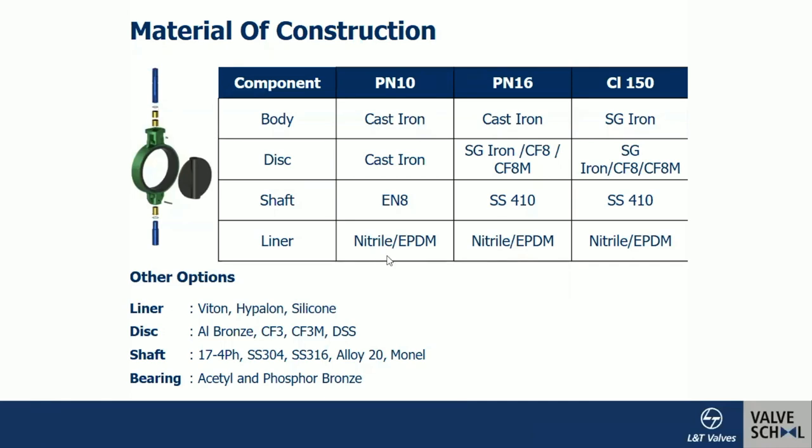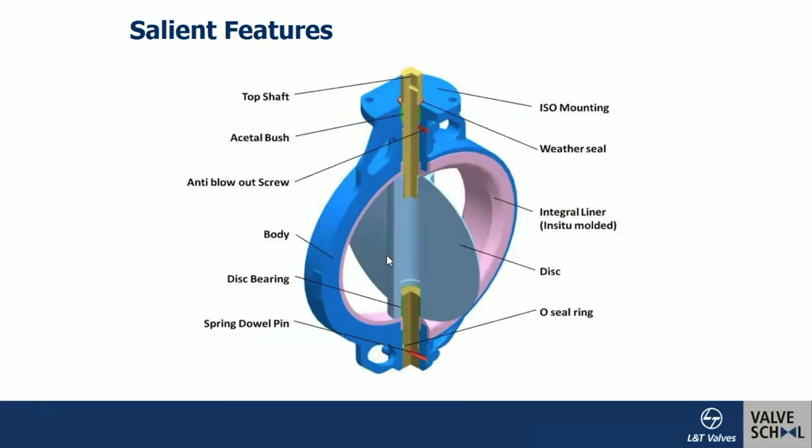Looking at salient construction features: when the valve is in the open condition, the disc is fully exposed to the line fluid. There is a top shaft and a bottom shaft. There is an anti-blowout screw — the stem will never come out of the body due to a dowel pin that goes into a slot on the top shaft. The body has an ISO mounting pad for direct fitment of actuators and gear units. An acetal bush with low coefficient of friction reduces friction between the body and stem.